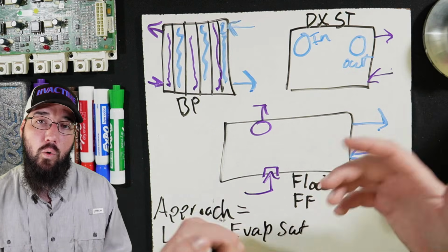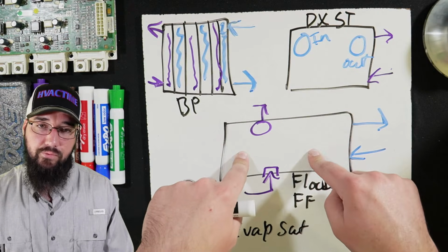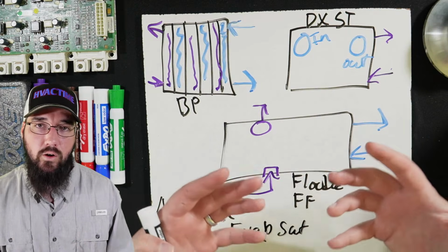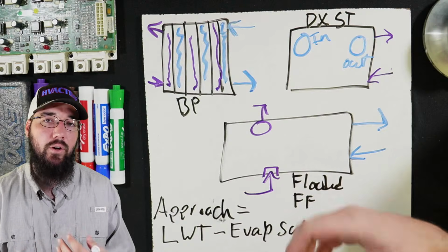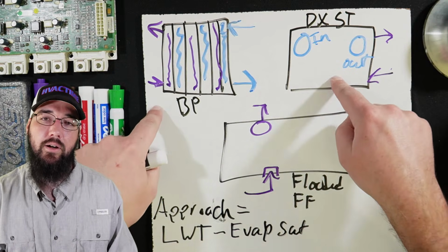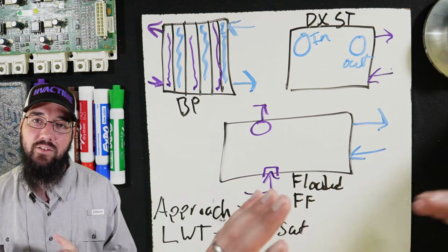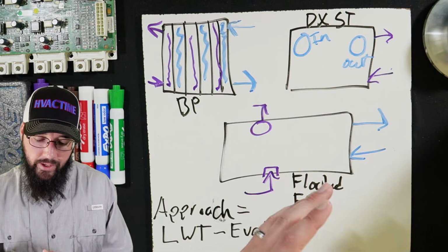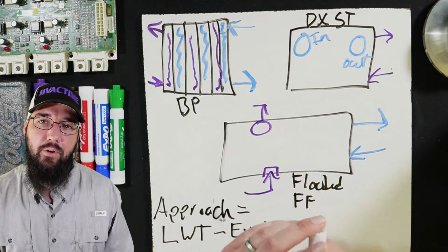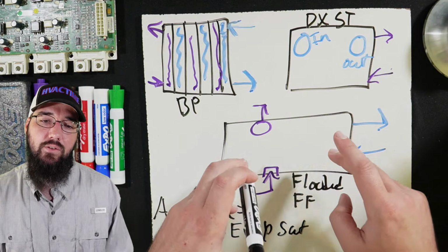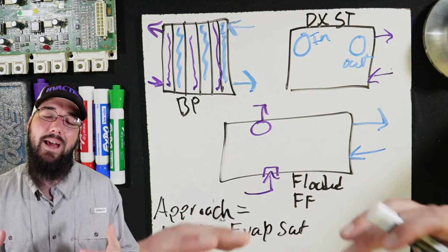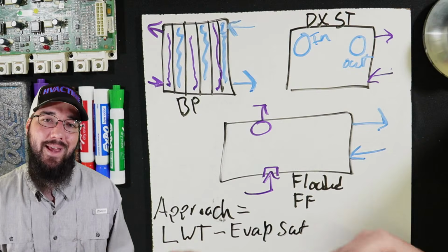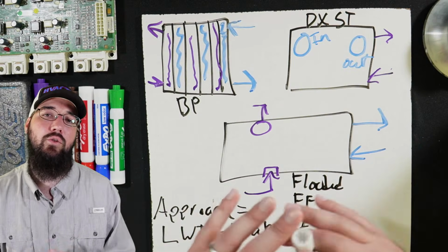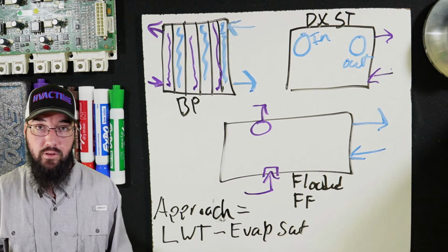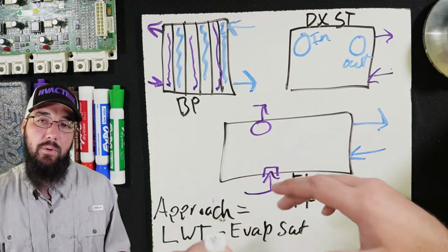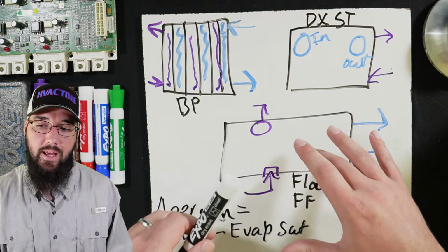They also don't have some of the same oil return issues that flooded and falling film have. So with these, you have to have oil mitigation where we're taking the oil back out of the evaporator. There's more to that process that these don't have to worry about. As long as you have enough velocity, another way to say that is differential pressure across your circuit, you can always get that oil back through that evaporator back to the compressors. That is not true with these. The falling film and flooded, that oil will get stuck in there, and we have to have some kind of oil recovery circuit in order to manage that, which adds a lot of cost and a lot of complexity to any machine. So it also impacts reliability to a degree. Oil migrating to the evaporator is a common call for machines that have these types of evaporators.